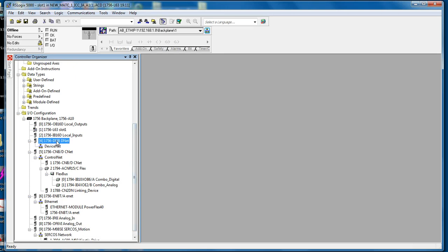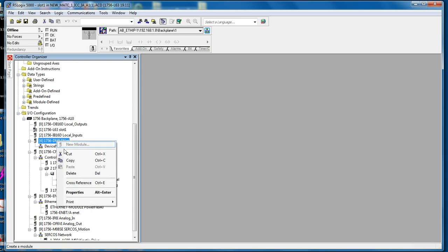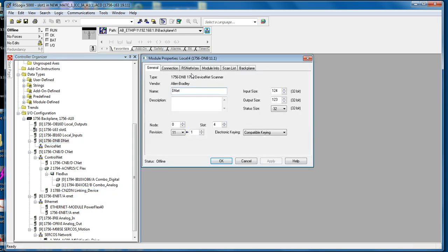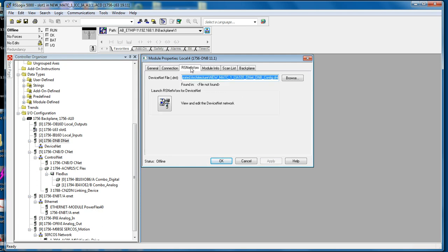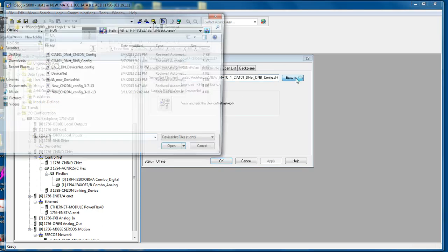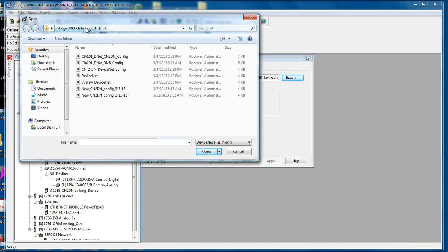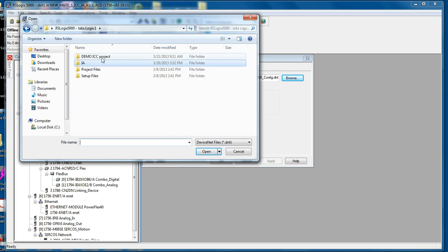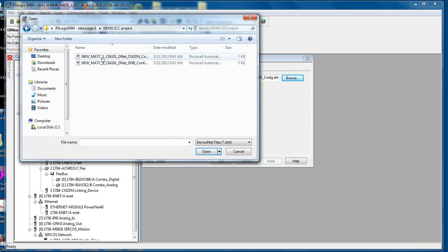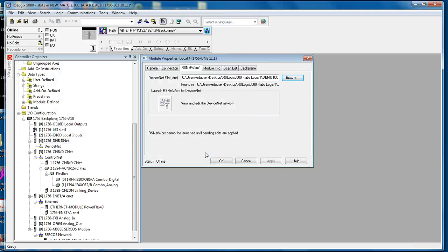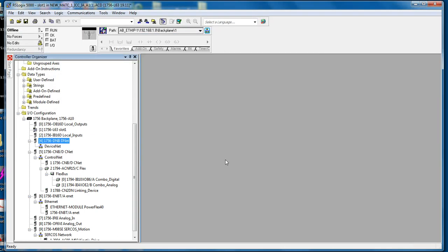To do so, click the slot number 4 for the device net, right click, select properties, go to the RSNetWorx tab, click browse, navigate to the folder. You see there are two configuration files. It only shows the ones that match the extension available. We want to use this DNB file. Since we're working with the DNB card, click apply and OK.